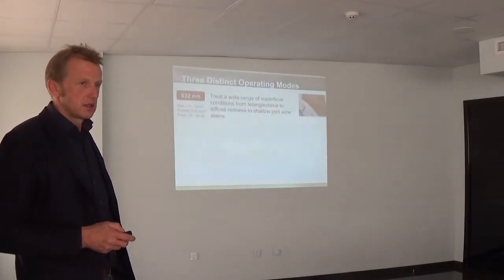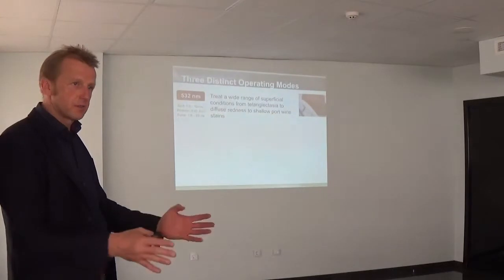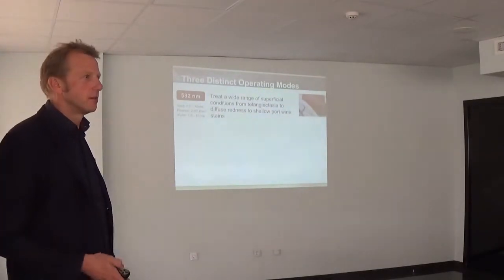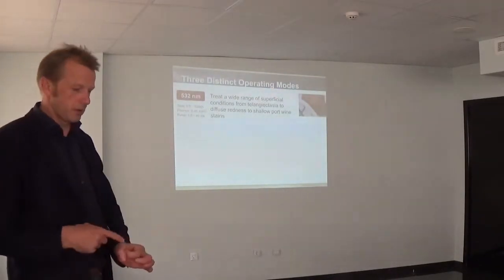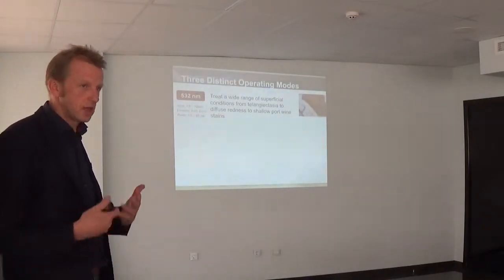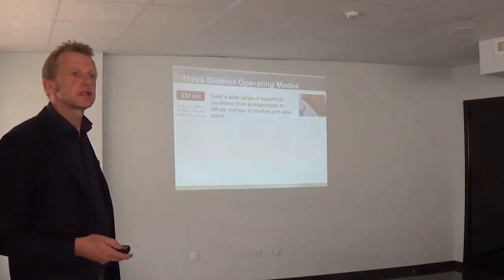If you compare that to the small KTP lasers on the market, small boxes, they have like 8 watts. So it's more than 100 times more power. And that's why we are able to get these big spot sizes with short pulse durations. That's what we need. That's why it's comparable to a pulsed dye laser.